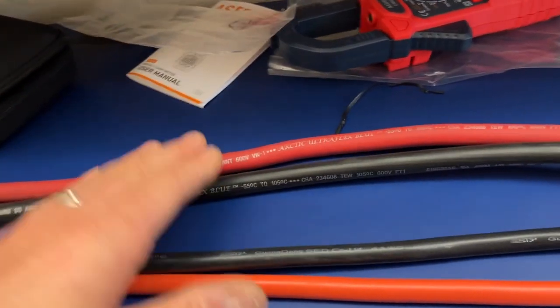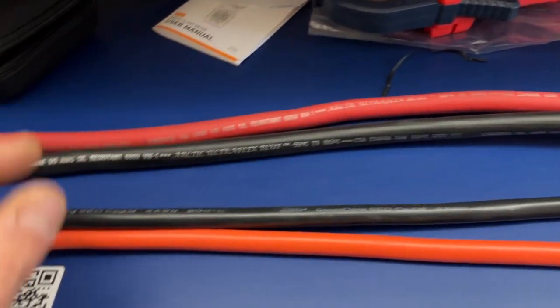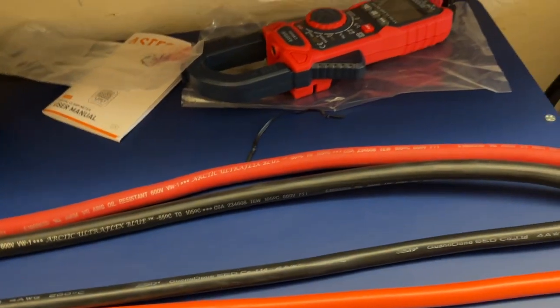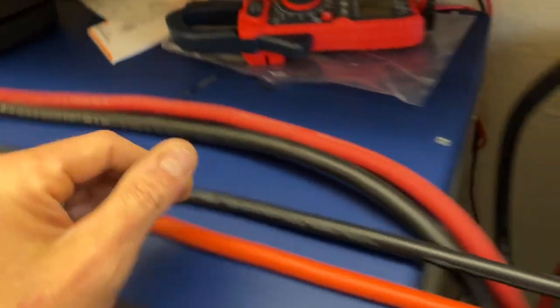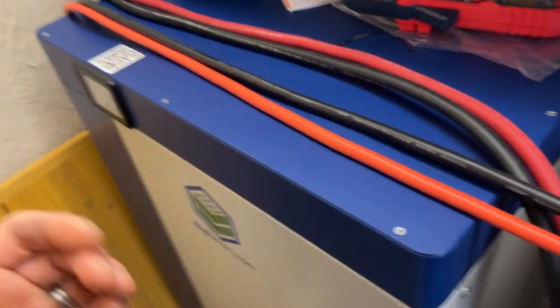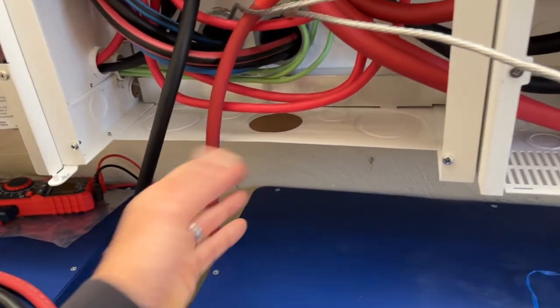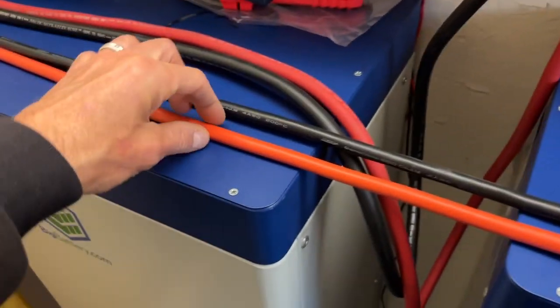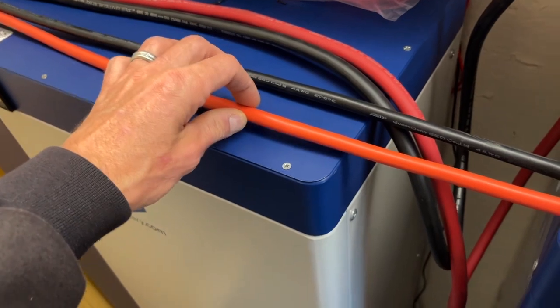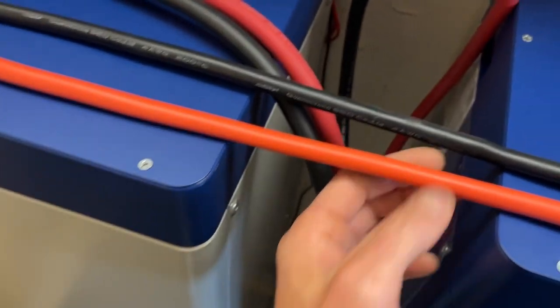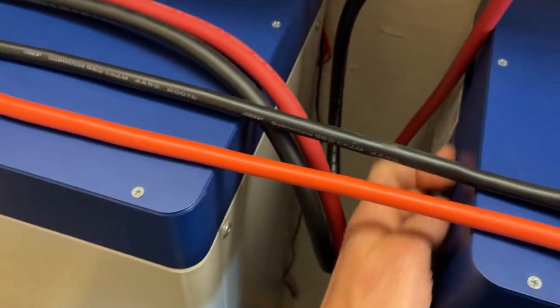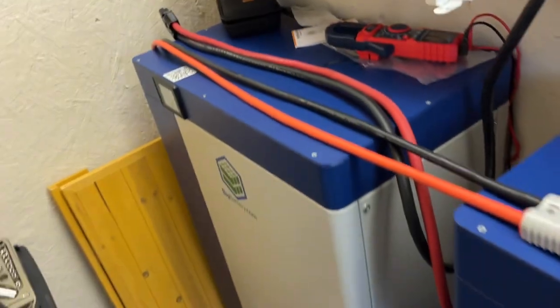And these are truly capable of carrying the current - they can carry 175 amps continuous. I've done all the research on wire size calculator.com, omni calculator.com. I went to three different sources to verify the wire size that would be required to run these going into a wire way. So once you're sitting free, these cables can actually handle it. But obviously that's how it's designed - plug it in here and these cables are just sitting free out in the open air.